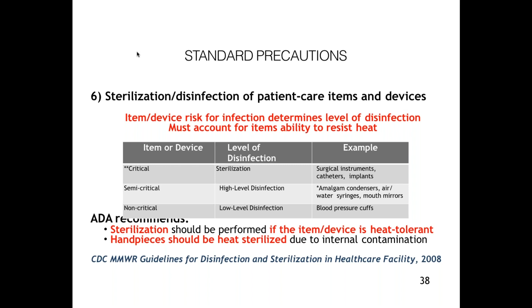All right. What about the temperatures, right? It gets very confusing here. I went to the CDC website, and I'm going to read you the numbers directly off of the CDC website. 121 degrees Celsius or 250 degrees Fahrenheit for a minimum of 30 minutes on a gravity displacement type unit. If you up the temperature to 132 or 270 degrees Fahrenheit, depending on the type of pack you're using, it can be as short as 4 minutes in a pre-vac type scenario. So the idea is if you turn it from 250 to 270, you can cut from 30 to 4, but you always have to follow the instructions for use based on the device and the packaging.